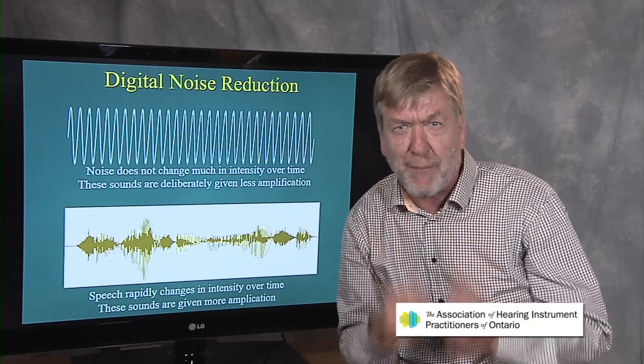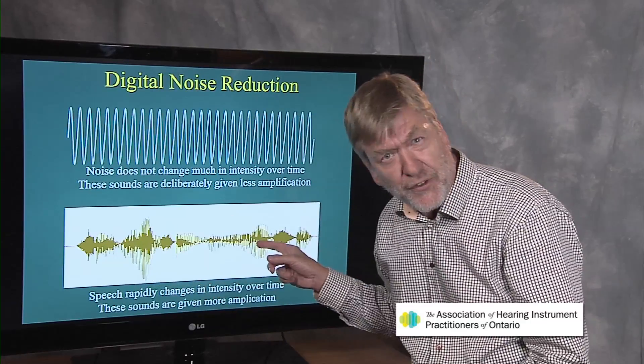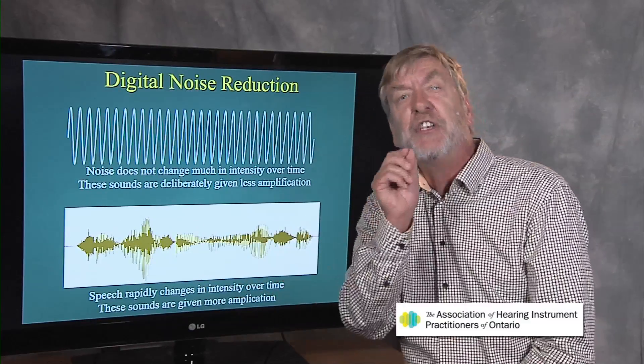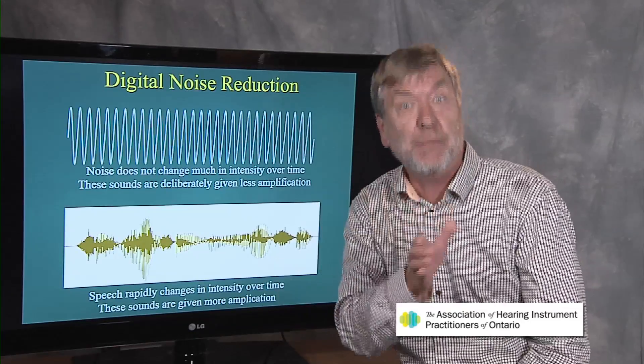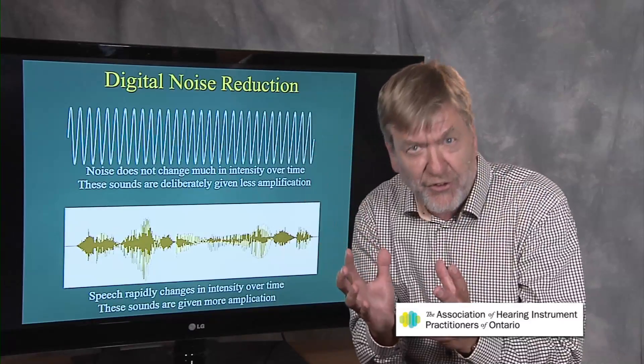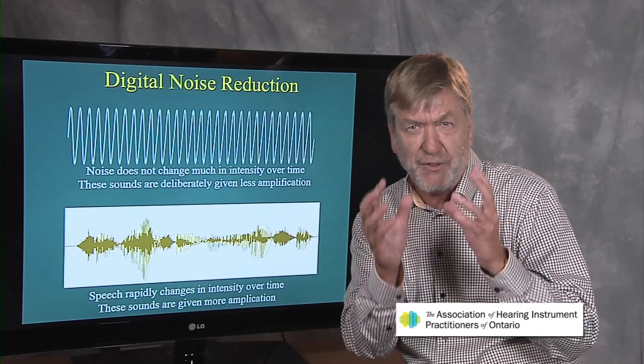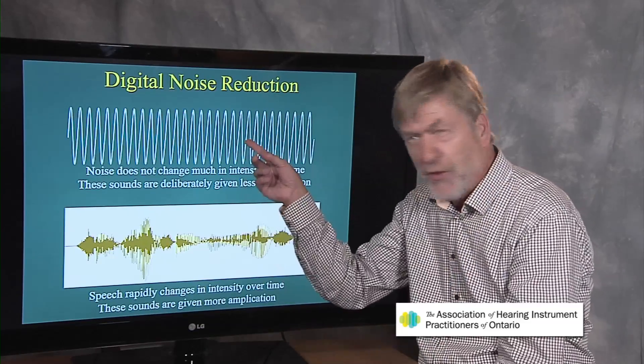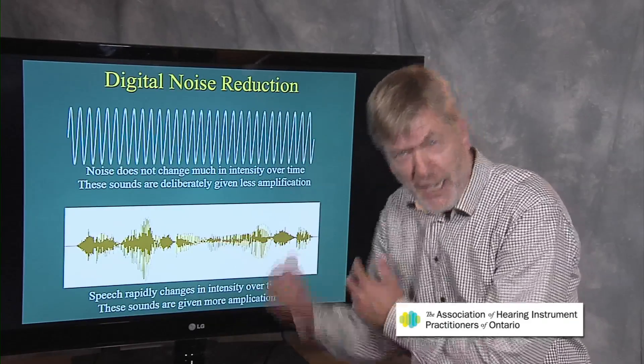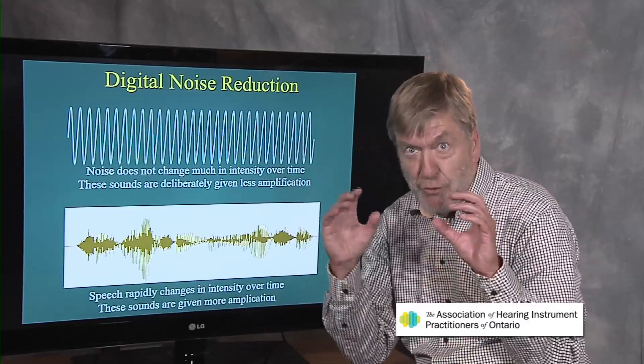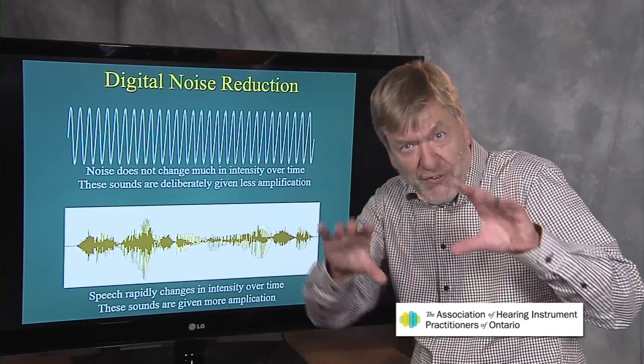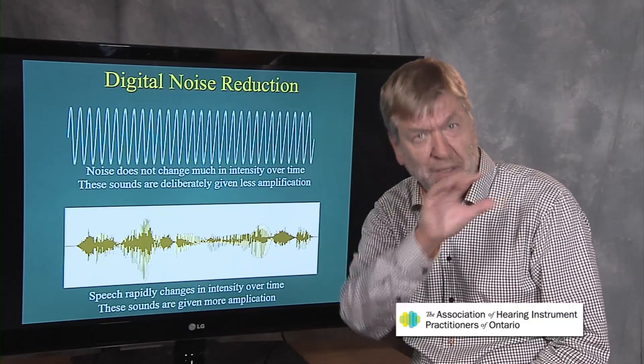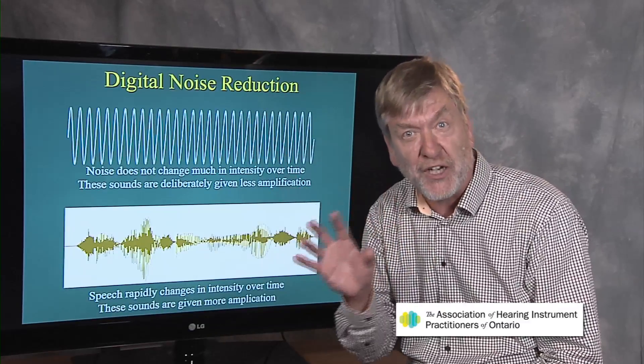But speech — the sound of my flapping gums right now — is totally different. Look at how it's changing rapidly over time. That's the uniqueness of the acoustics of speech. In digital hearing aids, we build in an artificial intelligence that allows the hearing aid to use statistics to ask: is the sound coming into my microphone more like a steady signal or more like a rapidly modulating one? If it looks like speech, amplify like crazy. If it looks like noise, reduce the amplification. The technique is to detect how much the amplitude of the sound is modulating or changing over time — that's digital noise reduction.